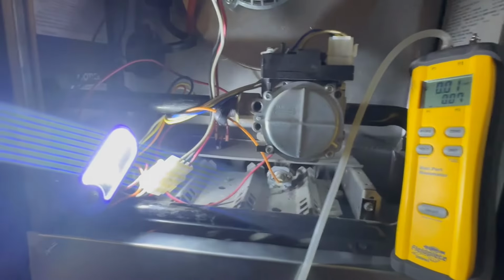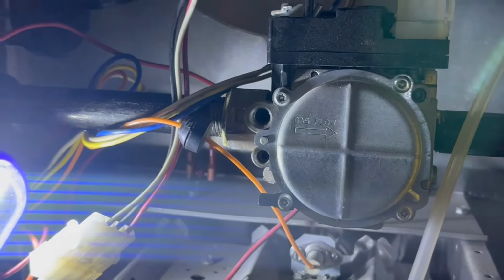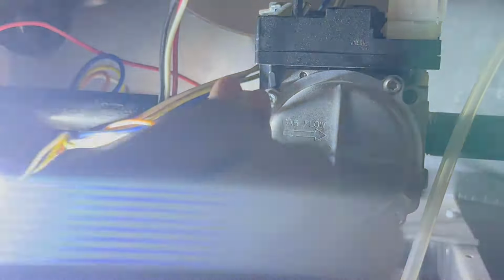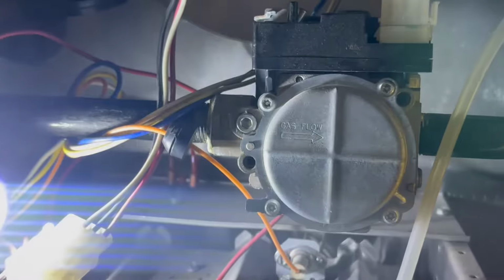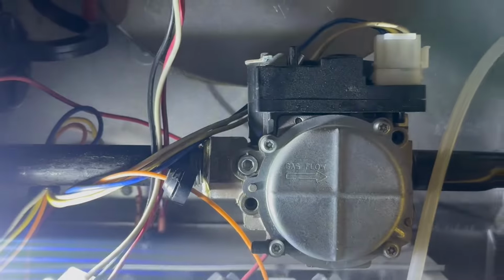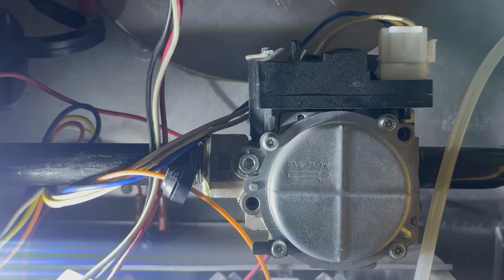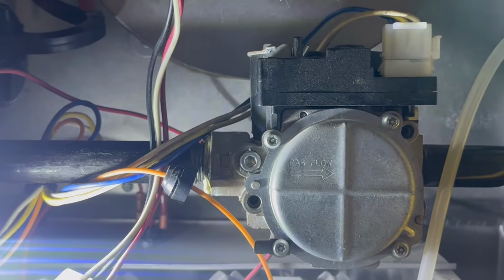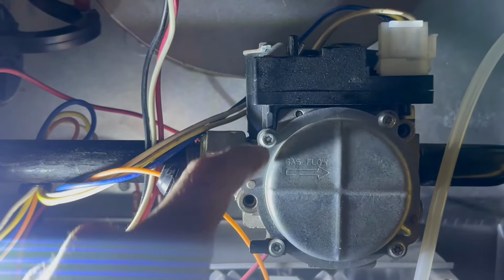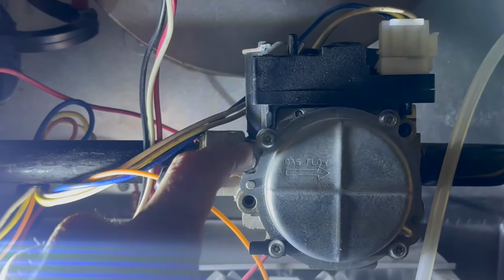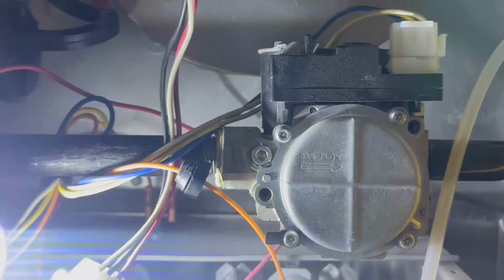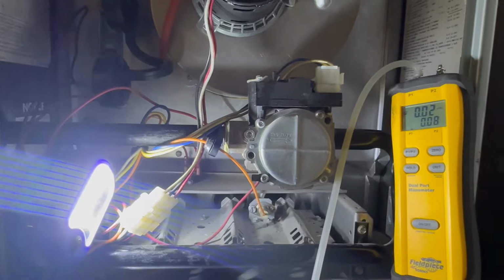So like I said, you're just gonna put it back where it was, and get your Allen key. And then once you feel like it's tight, you're good. Righty tighty. Okay, and that's good. And then you can do a simple test. You can open the gas valve, maybe use some soap and bubbles to see it's not leaking out. But normally, once you put it back in, you'll be fine. But this is how you would check this gas valve.